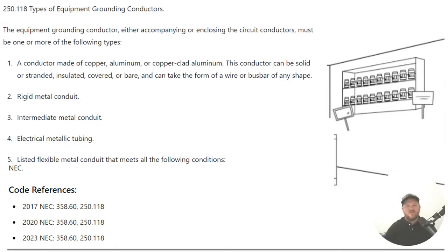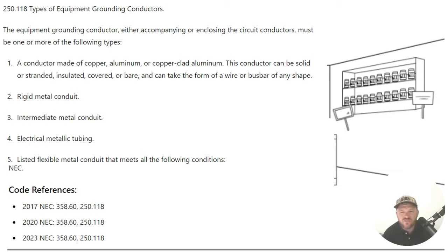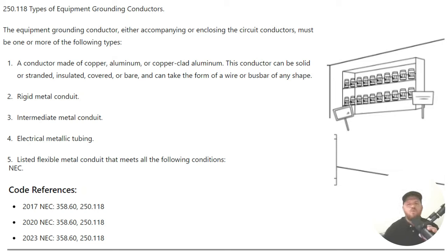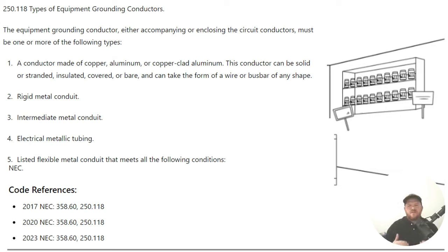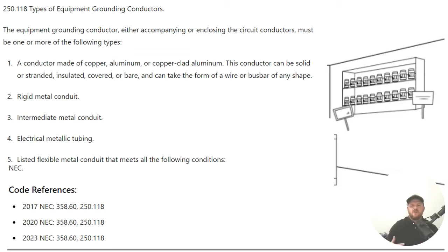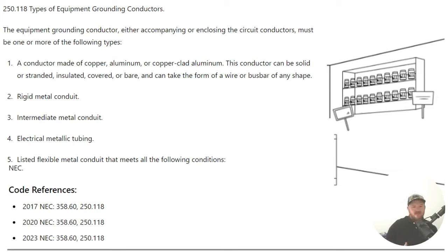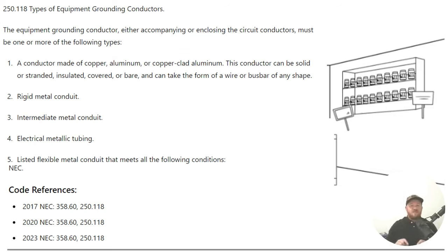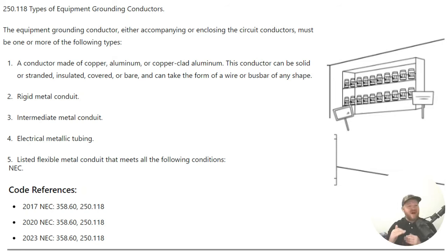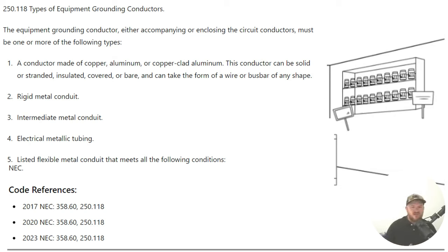Let's look at the paraphrase code language here. It says the equipment grounding conductor, either accompanied or enclosed with the circuit conductors must be one or more of the following types. The first one is a conductor made of copper, aluminum, or copper clad aluminum. This conductor can be solid, stranded, insulated, covered, or bare, and can take the form of a wire or bus bar of any shape. So that's the one that we're most familiar with. It's called a wire type or a bus type equipment grounding conductor. The one that we're most familiar with is a wire type, the green, stranded, bare, solid wire that you install with your circuits to act as the equipment grounding conductor. That's the one that we're most familiar with.